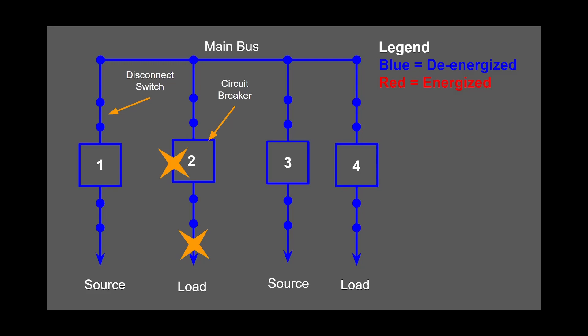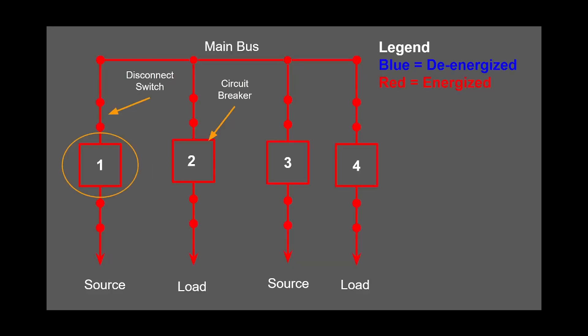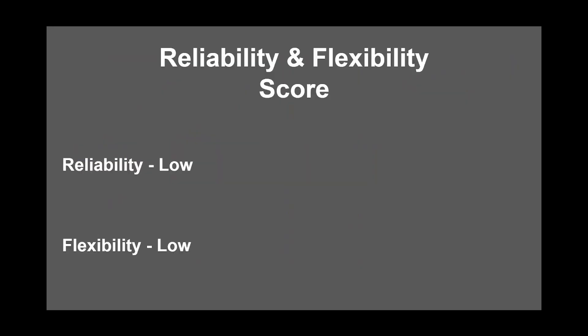Let's determine the flexibility. Let's assume that circuit breaker one needs maintenance. As soon as this breaker is tripped, everything downstream would no longer be energized. Same for all of the breakers, making this configuration low on the flexibility scale.